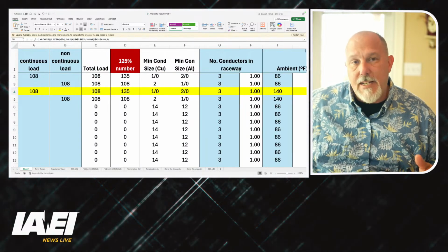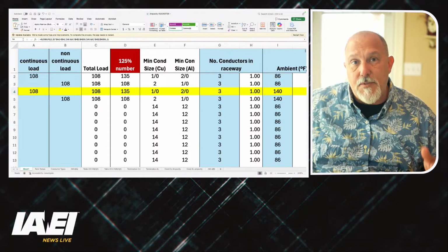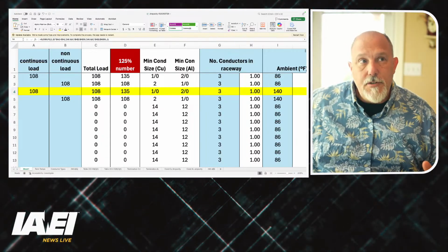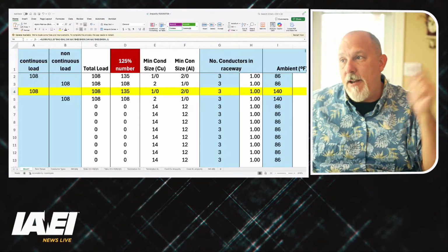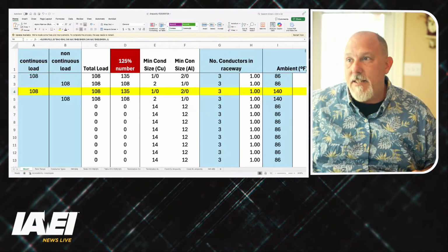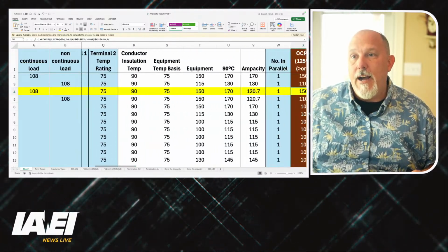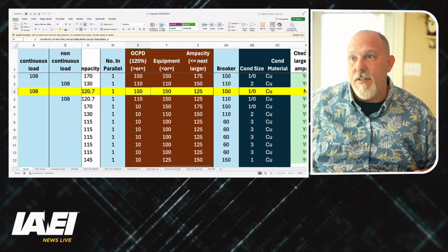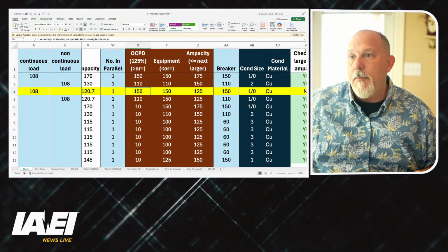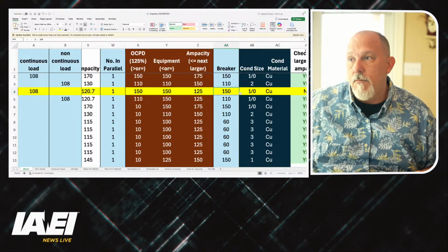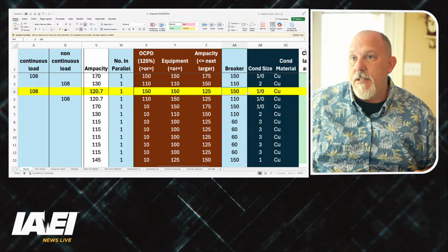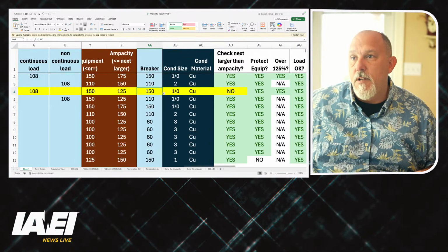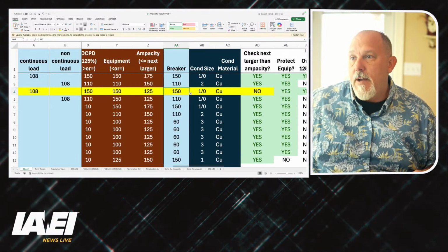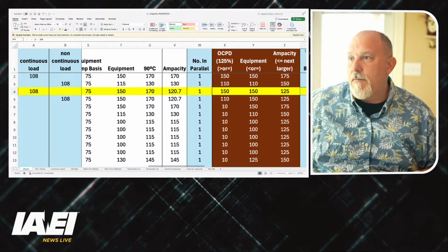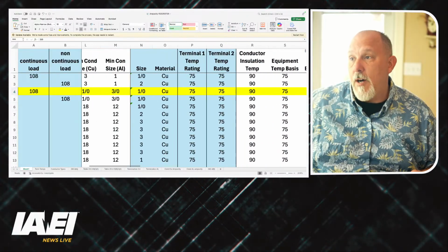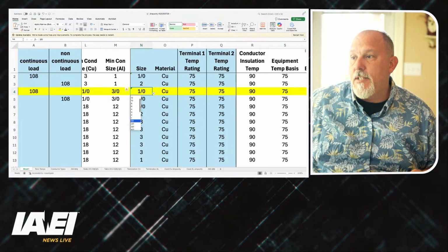108 amps at 125% is 135 amps, remember. So my overcurrent protective device can't be less than 135 amps because of the rule in 210 that tells me my overcurrent device has to be greater than 125% of the continuous. So a 125 amp overcurrent device isn't going to work. I pick 150, and I had to increase the conductor size because of this right here. I have to go from a 1/0 to a 2/0.